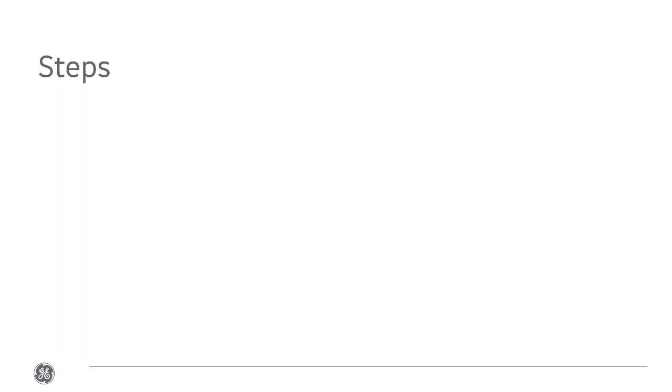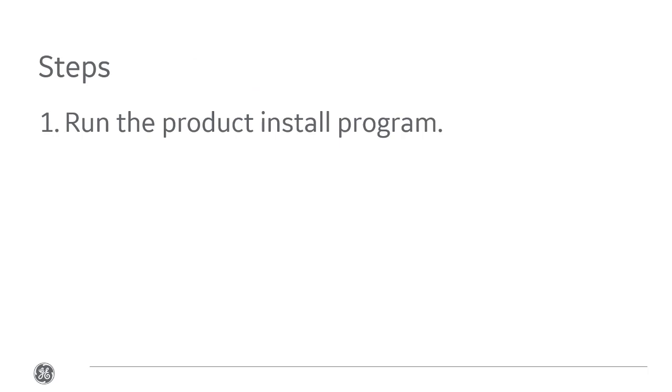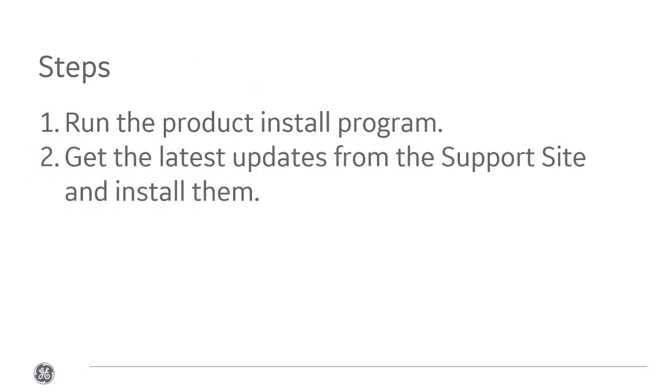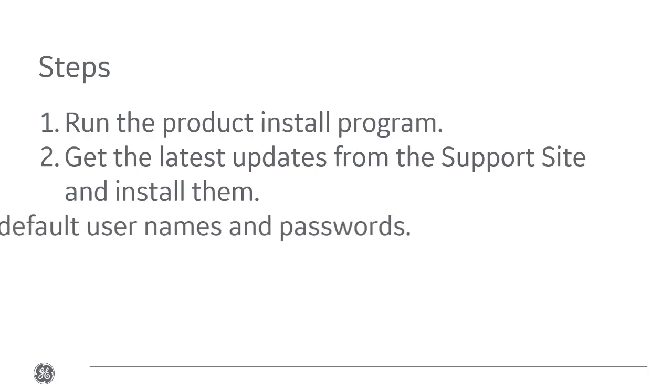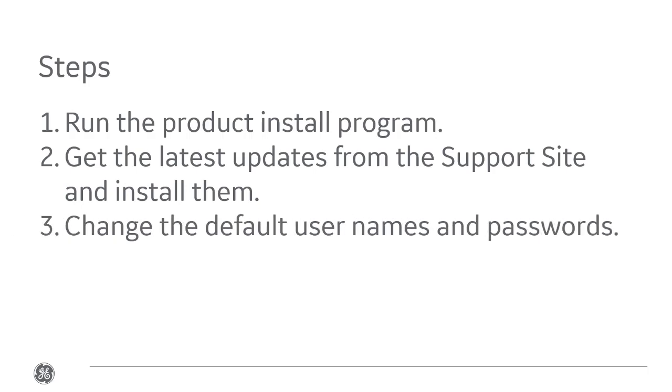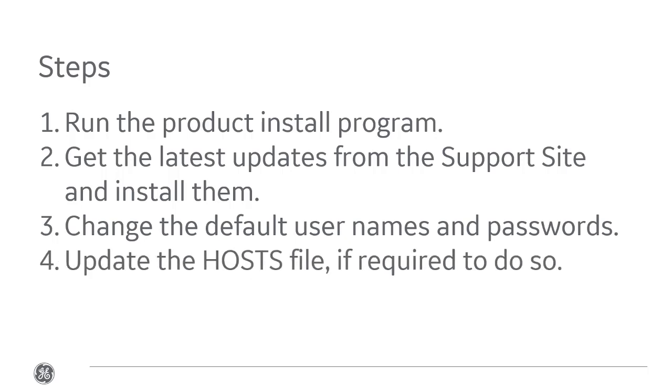There are four steps to install iFIX. Number one is run the product install. Number two, get the latest updates from the support website. Number three, for security purposes, change the default usernames and passwords for iFIX. And number four, optionally update the host file if you're required to do so.